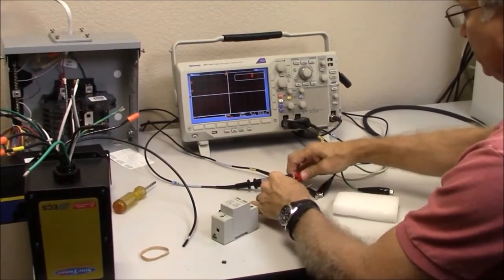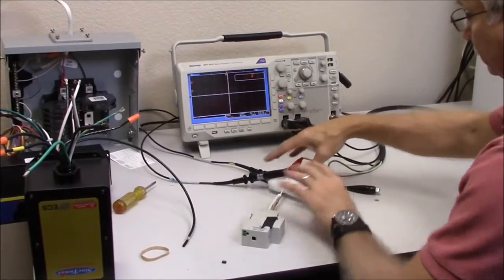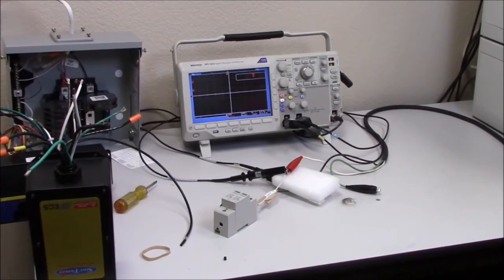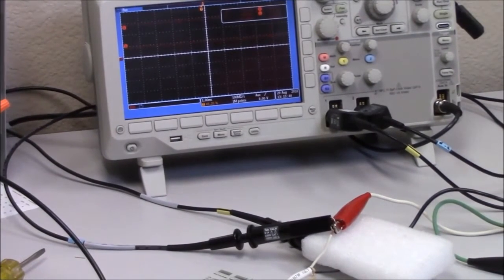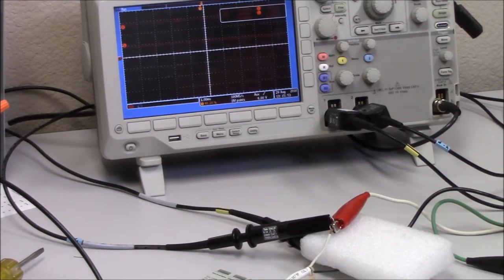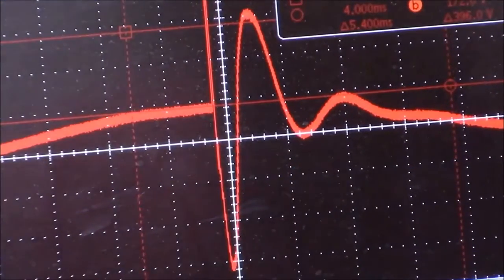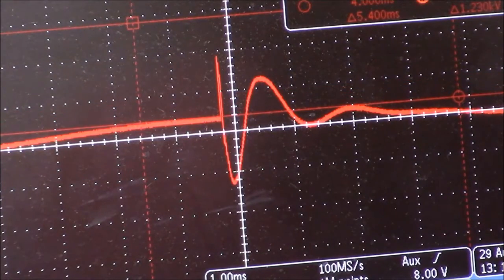Okay, let's remove this unit and test the typical unit found in many panels. This is the DIN rail mounted type device, again line to neutral. Apply power, charge the generator. The generator is about to release the surge. Light spark there and this unit has actually gone off the scale a little bit so let's zero it back in.